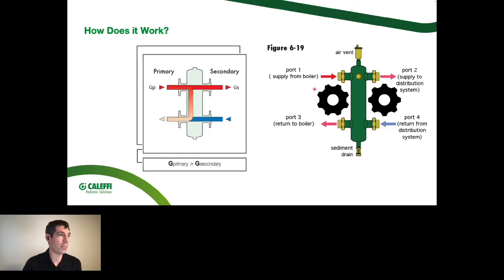However, I would say most of the time, we're going to have some difference in a multi-zone system. Or let's say we have multiple boilers or something like that, where it's not just a single boiler that's on and off, but it's 4 boilers that are cascaded together. In that case, we could have, let's say, 10 GPM on the left side and then 5 GPM on the right side. Maybe the building is pretty well up to temperature. The sun came out. There's only one zone calling. We've got an ECM circulator, so that's slowed down on the right side. But the boiler needs to maintain a minimum flow rate to stay happy with whatever that single speed pump is. In a simple example, this is a case where inside of that hydro separator, we're going to have 5 GPM just go right back to the boiler. So to keep that 10 GPM that we need for the boiler heat exchanger, 5 GPM are just going to peel right off and go back to the return of the boiler or the heat pump or whatever the case may be.